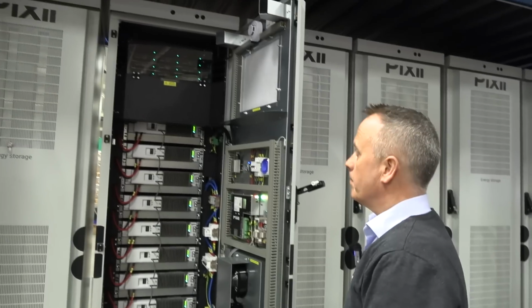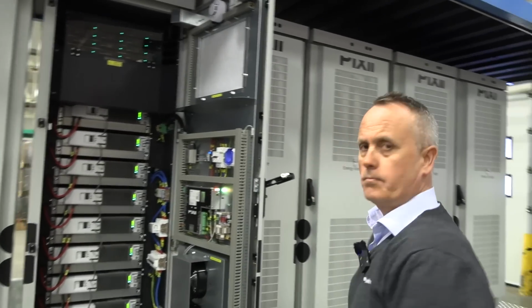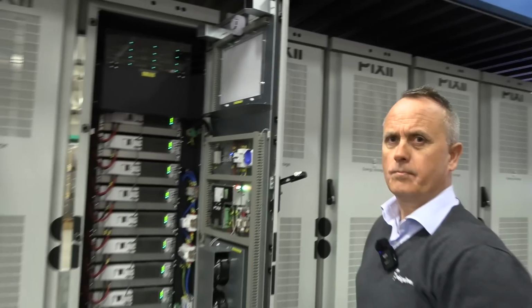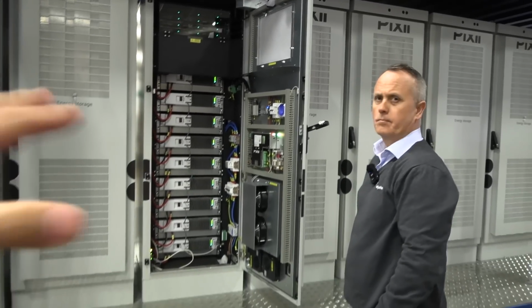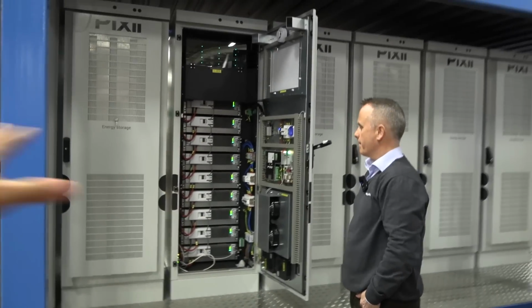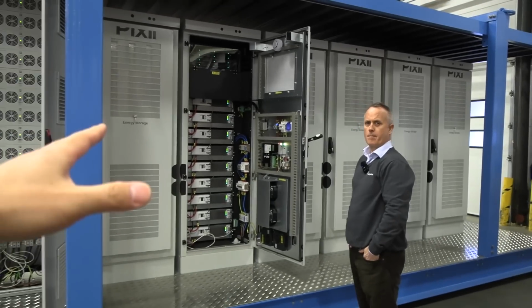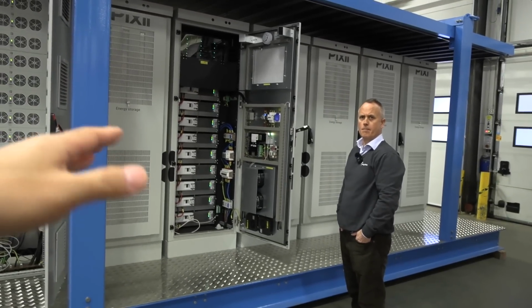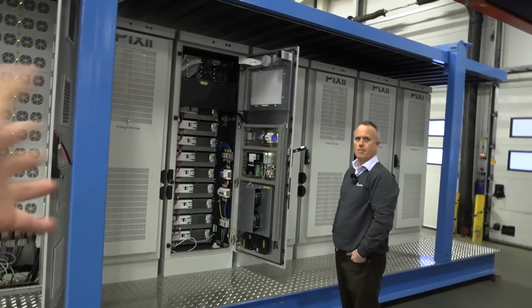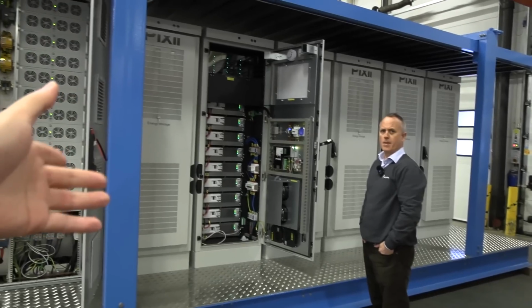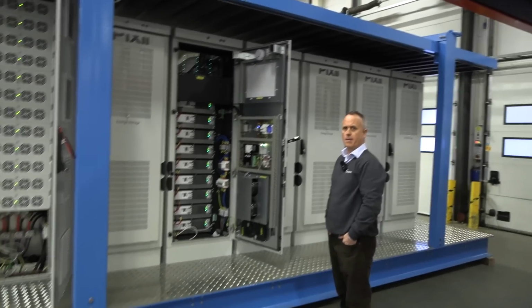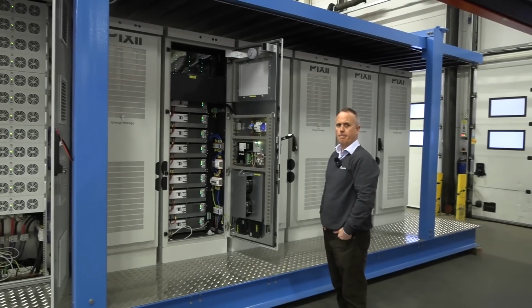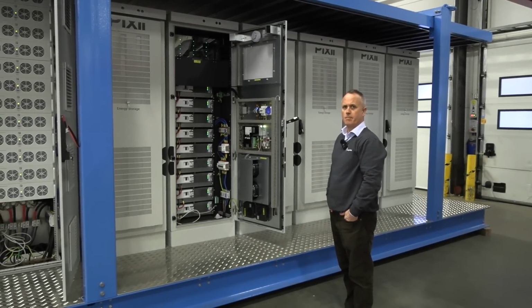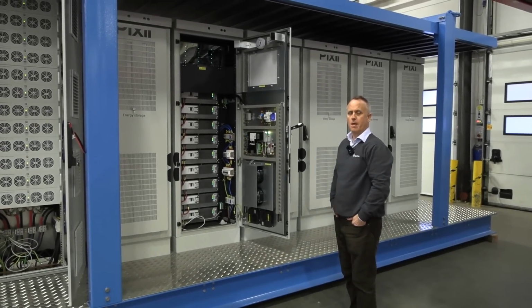And I should mention, in case it wasn't clear, that this whole package here is 300 kWh, and it can actually discharge 300 kilowatt, or technically also charge at 300 kilowatt. But it only needs to be fed with 43 kilowatt AC, minimum 43 or more.